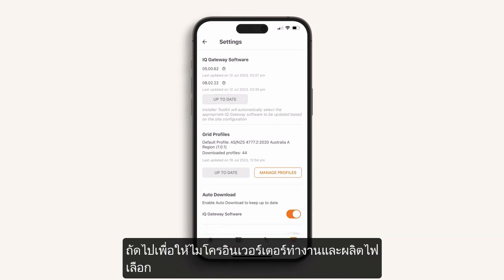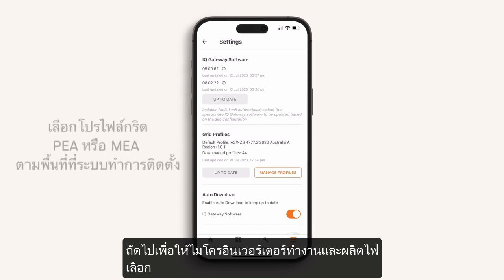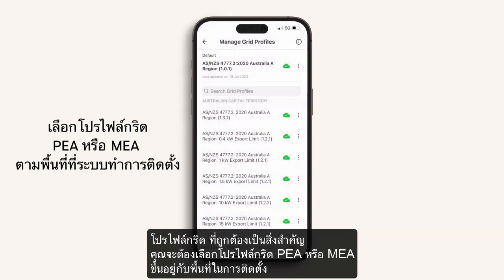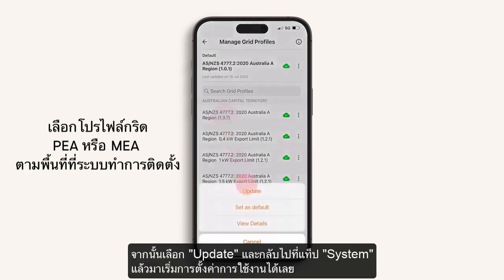Next, for IQ8 microinverters to power up and operate, it is critical to select the correct grid profile. You will require minimum version 1.3.7 of grid profile. Select from the list and then select update.